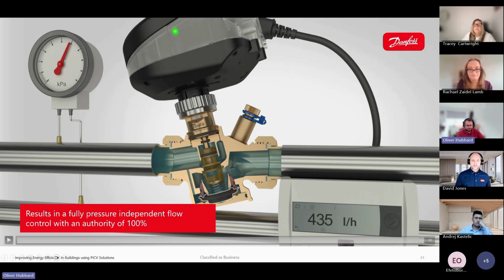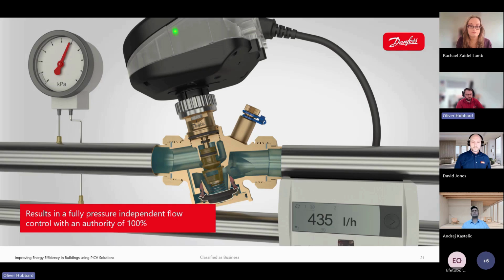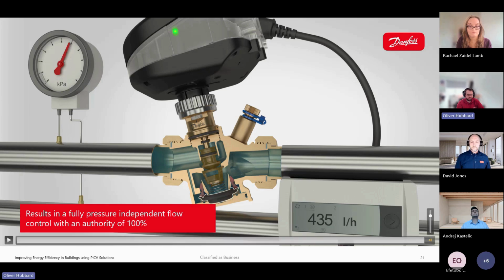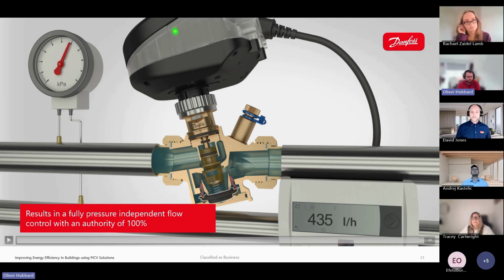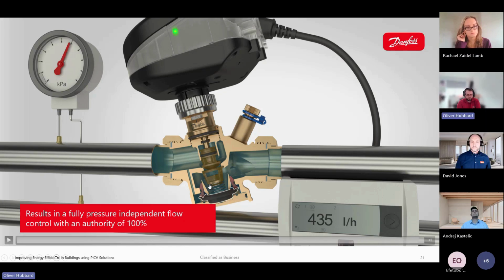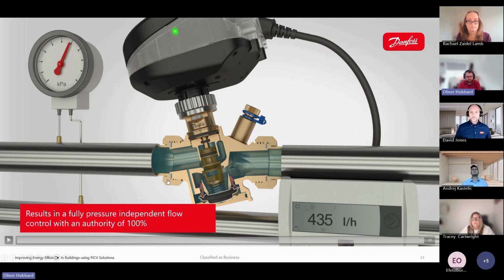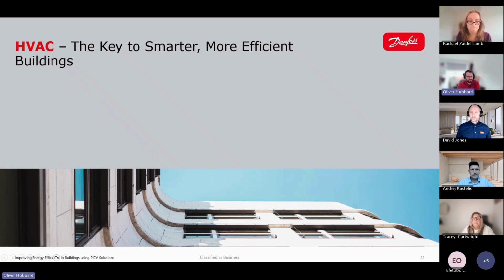By limiting the flow mechanically inside the valve, we effectively reduce the working stroke range of the control element to only what's required for that design flow. That improves modulation quality and stability. The result is fully pressure independent flow control, meaning the valve always operates with 100% authority. In other words, the control valve has complete control over the flow at all loads, with no influence from system pressure changes, delivering accurate temperature control, simplified commissioning, and guaranteeing hydronic balance. Next slide.